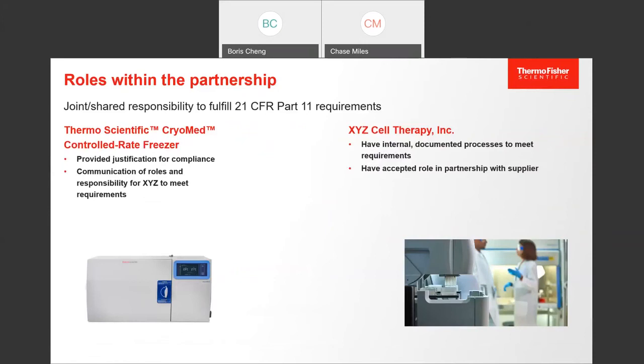So again, reflecting back: clear rules of engagement for the manufacturer, clear rules of engagement and requirements they must meet for XYZ Cell Therapy Company. From an equipment manufacturer side, I've got to be able to provide justification for compliance to my auditors, and I need to communicate the roles and responsibilities that XYZ needs to take over in order to maintain 21 CFR Part 11 requirements. XYZ is going to have documented processes, and they have to accept their role within the partnership with the Cryomed manufacturer. They have to physically do things with the outputs of the CryoMed controlled-rate freezer - so they're signing up for something, and we as the manufacturer are signing up as well.